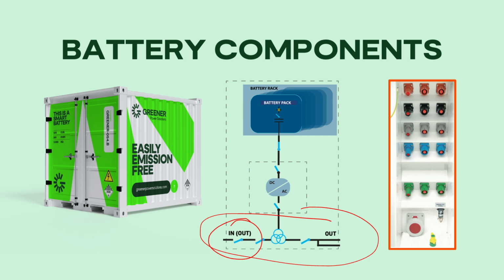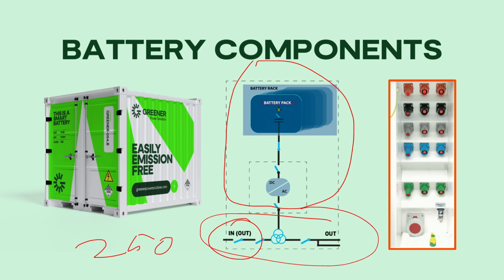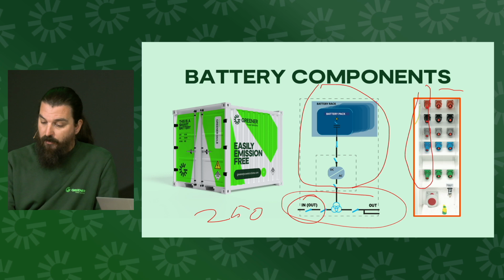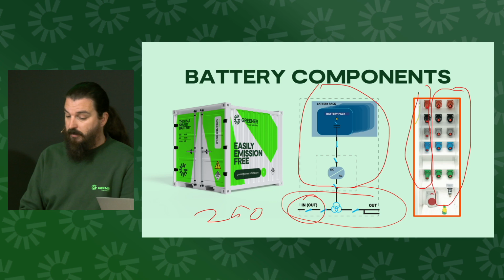So this input is 250 kilowatts. So ESI is an energy storage inverter? Yes, so that would be the entire thing of the batteries and the inverter together. So we have an input which is 250 kilowatts, 400 amps. So that's a single set of power locks. And we push them through to the output, and then on the parallel there is the inverter, which is also rated at the same 250 kilowatts, 400 amps. So that means that on the output we have the double capacity available. So that's 500 kilowatts, 800 amps.